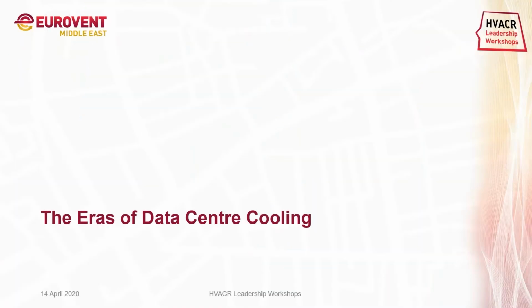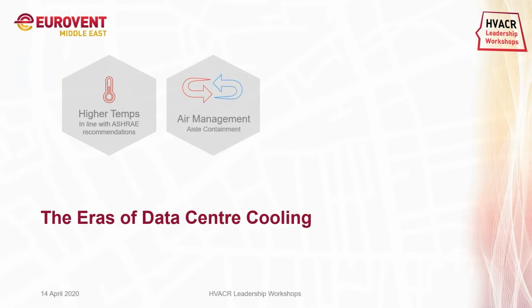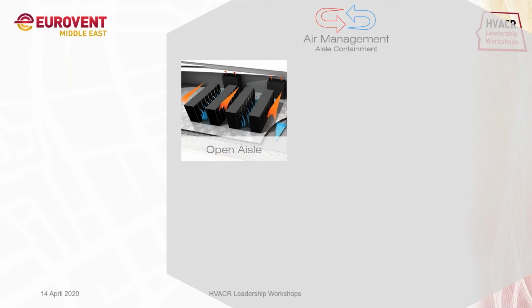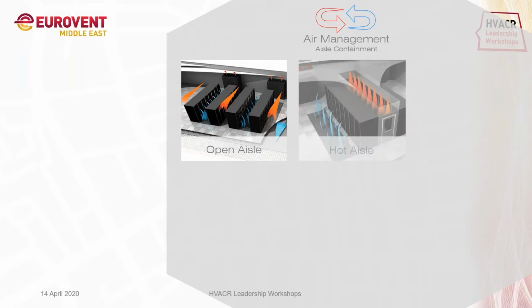Going to the eras of data center cooling, we have seen higher temperatures in server rooms and data centers in line with the ASHRAE recommendation by the year 2011. We have seen efficient air management by aisle containment by the year 2008. Going to the aisle containments, there is the open aisle architecture where there is a mixing of air, there is no containment, the cold air is supplied and the return air goes to the open space. Then we have the hot aisle, where the hot air, as you can see in the orange or red color between the racks, is contained.